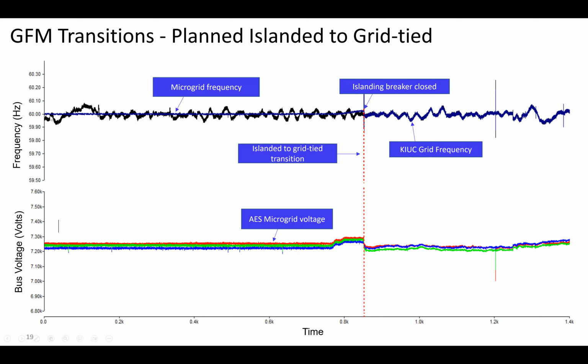So we start here in microgrid mode. Again, frequency versus time. The blue line here is the microgrid frequency. The black is the KIUC grid frequency recorded. So we're in islanded mode, disconnected from the grid. We initiate a planned islanded back to grid tied transition and go through the sequence. We obviously perform a sync check prior to closing this islanding breaker, bring the frequency and voltage of the microgrid back in range with the KIUC grid, as well as match the phase angle, close the breaker here, and now we're grid tied, and we continue our dispatch to the grid.